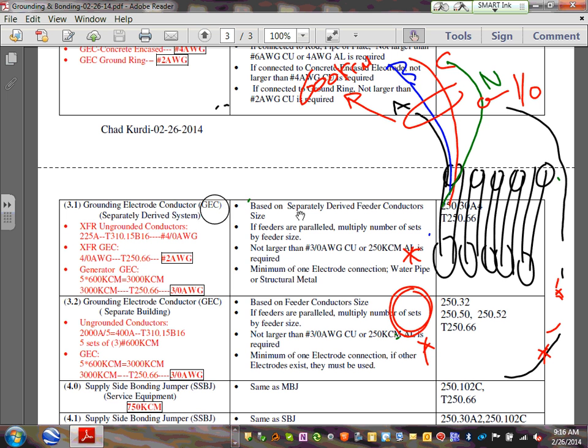So your 3.1, I want to bring to your attention that we are doing it for the transformer, for the generator. 5 times 600 kcm. Why 600 kcm? Because remember, we're carrying 600 kcm, 5 of them. That gives you 3,000. 3,000, take it to 250.66. Hey, don't go larger than 3 aught. No need. Unlike the system bonding jumper, where you start multiplying by 12.5%. Grounding electrode conductor, stop at 3 aught.